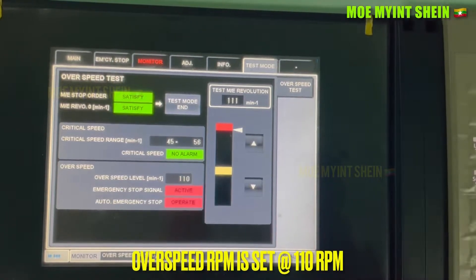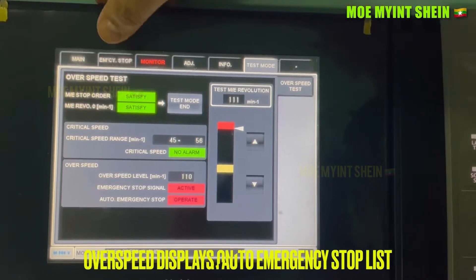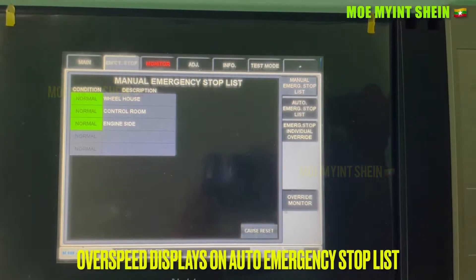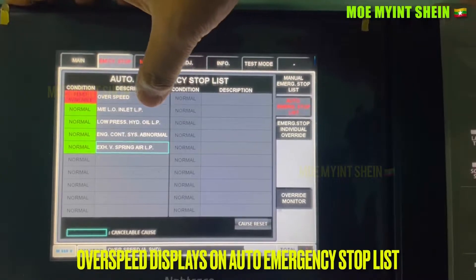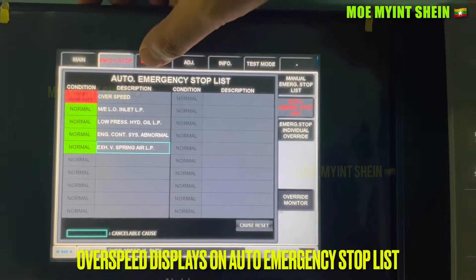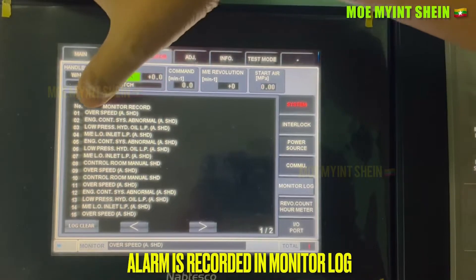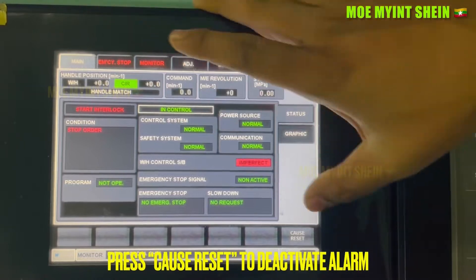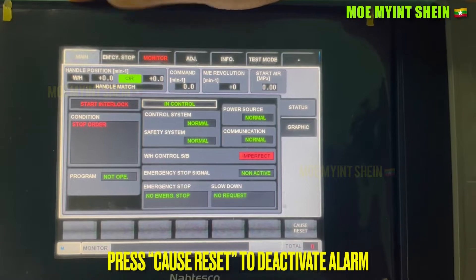When RPM reaches 110 RPM, the emergency stop signal activates and over-speed trip will happen. Over-speed trip also displays on the auto emergency stop list. Activated alarms are also recorded in the monitor log of the control system. Press the cause reset button on the screen to deactivate the alarm.